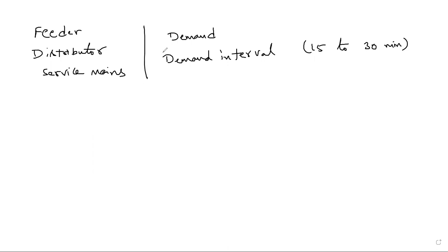What is meant by the load duration curve? We can also call it a daily demand curve. It shows how the load varies with respect to time over a specified period of time. That means when the on-load peak demand is present and when the off-peak load is present, everything we need for the analysis comes from this load duration curve. We need to consider the total time period, that is 8,760 hours, your 365 days multiplied by 24 hours.